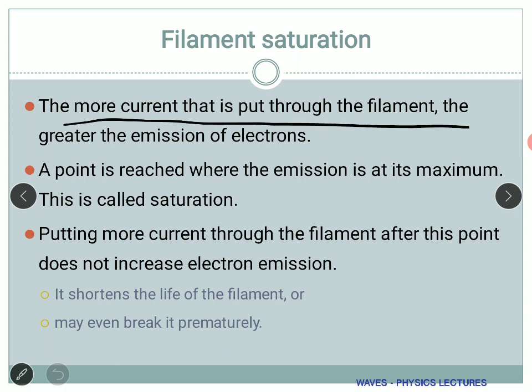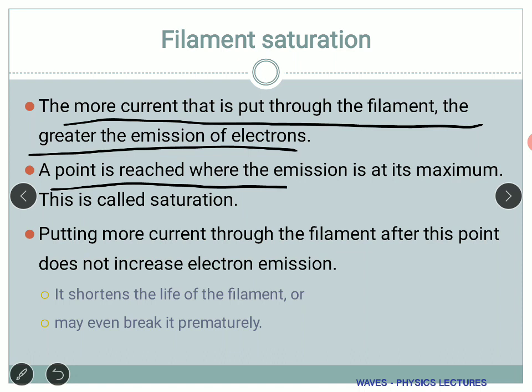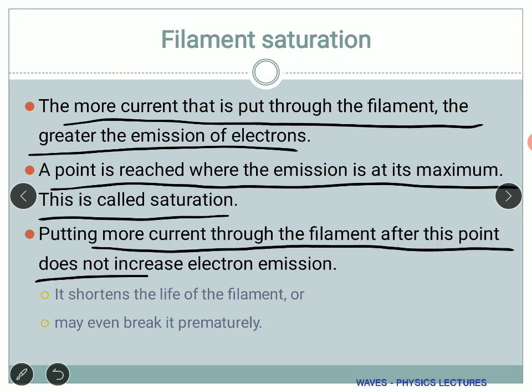There is something called filament saturation. The more current put through the filament, the greater the emission of electrons — but there is a point where emission is maximum and you get no more additional electrons. This is called saturation. Putting more current through the filament after this point does not increase electron emission; in fact, it shortens the lifetime of the filament or may even break it prematurely. People operating these instruments are experienced and know the input requirements to maintain longevity.